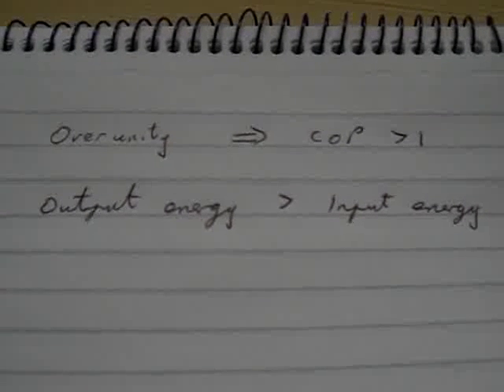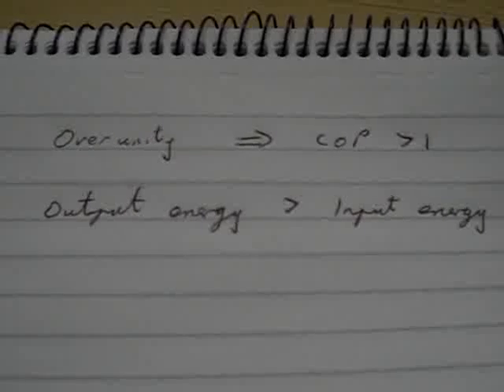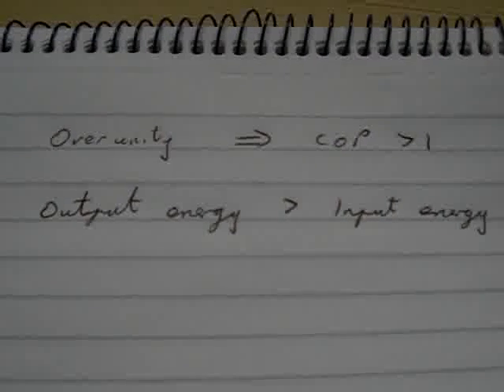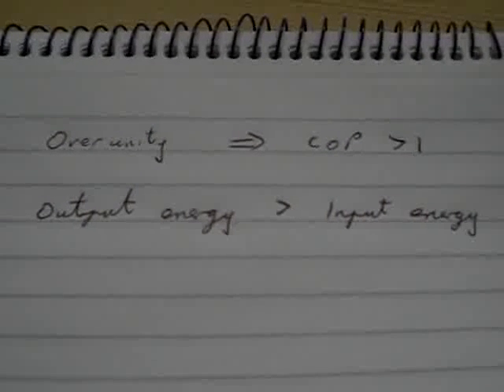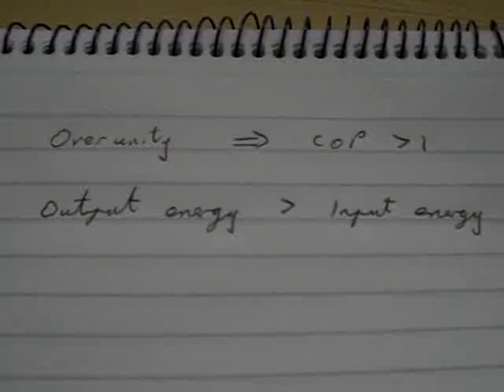Whereas if we were just to run an electric fire or an element heating water, then of course that's one kilowatt energy in would give us one kilowatt of heat energy out.